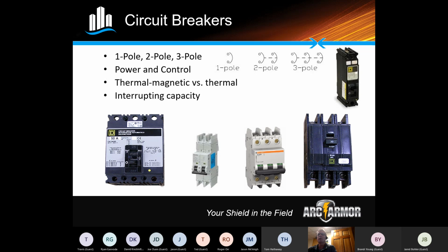Why is that important, right? It's important because a few years ago, UL and NFPA came out and said that panels also have to have an SCCR rating. So what's an SCCR rating? Well, it's the rating of the panel; SCCR stands for short circuit current rating. And the difference between an interrupting capacity and an SCCR is that an SCCR covers all the components within the panel that make up that number, whereas the interrupting capacity is just for that particular component.